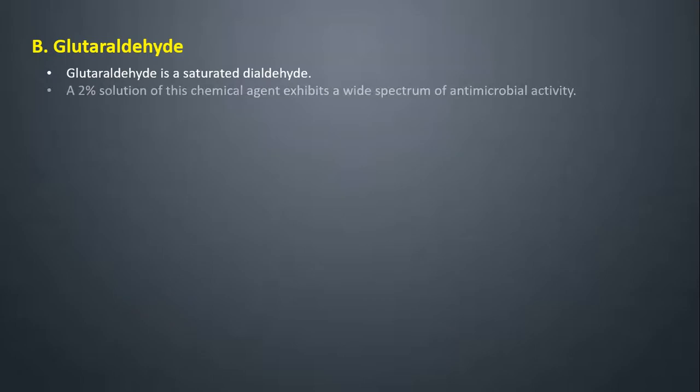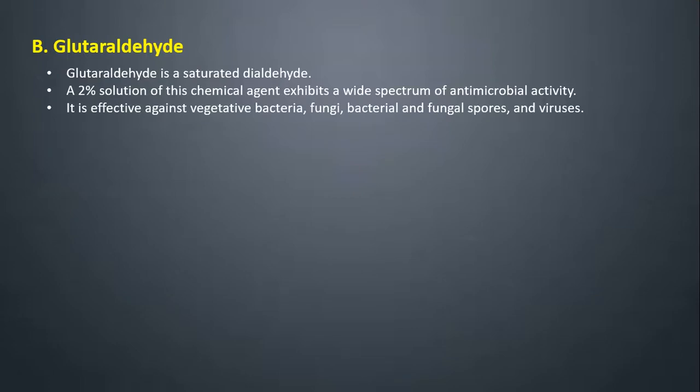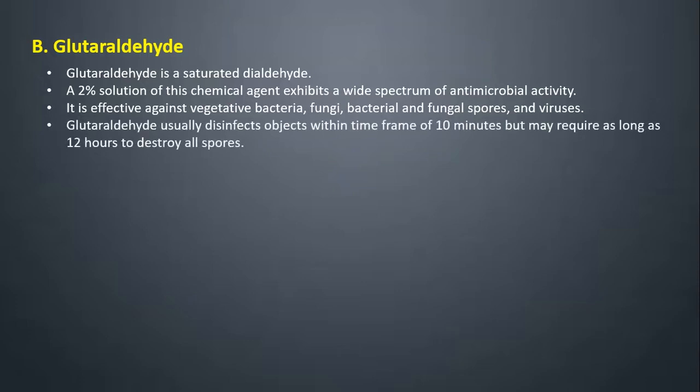Glutaraldehyde. Glutaraldehyde is a saturated dialdehyde. A 2% solution of this chemical agent exhibits a wide spectrum of antimicrobial activity. It is effective against vegetative bacteria, fungi, bacterial and fungal spores, and viruses. Glutaraldehyde usually disinfects objects within a time frame of 10 minutes, but may require as long as 12 hours to destroy all spores.